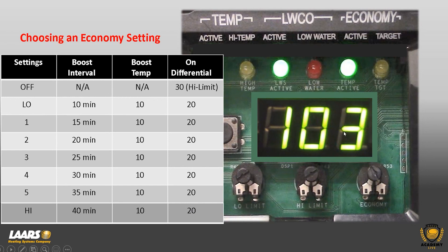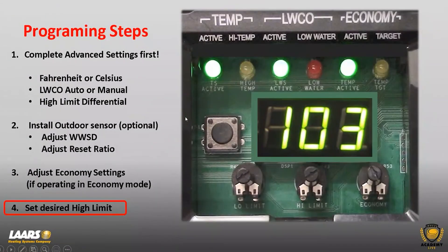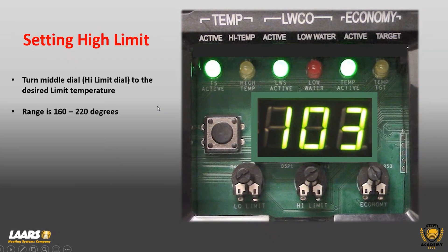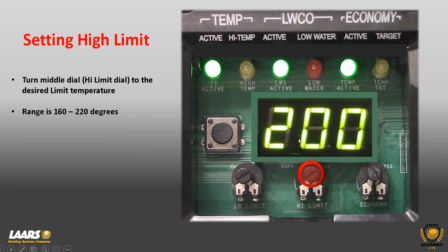Lastly, set your desired high limit using the middle dial. The high limit range is from 160 to 220 degrees and adjusts in one-degree increments. In this example, I'm showing 190 degrees — turn it again and it goes to 200. This is not a manual limit; it is an auto limit. At 200 degrees the boiler shuts off, and with the default 30-degree differential, at 170 degrees it would refire.